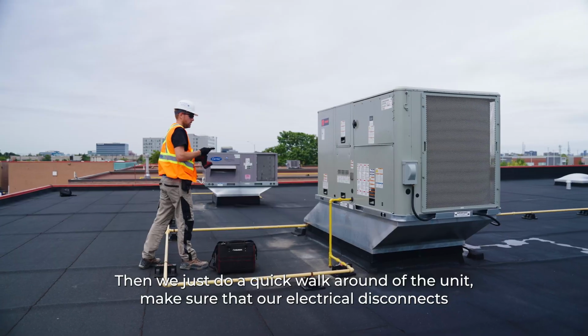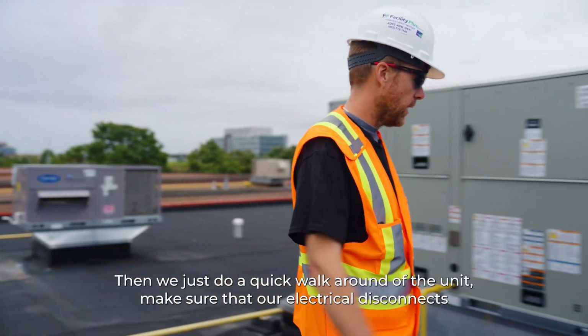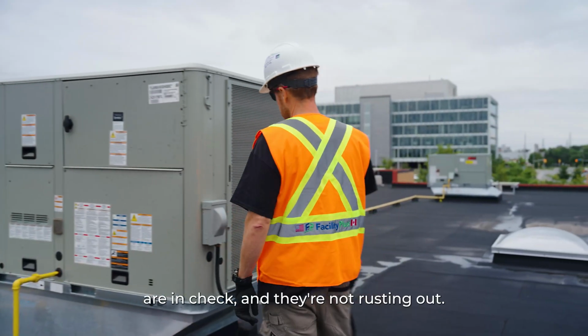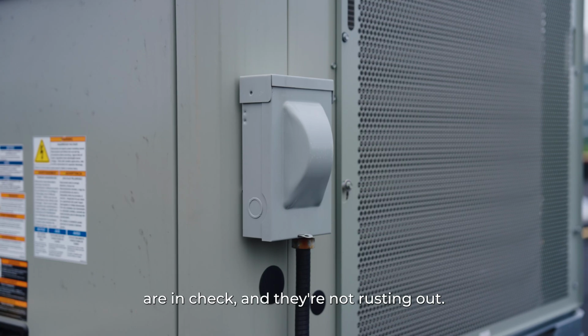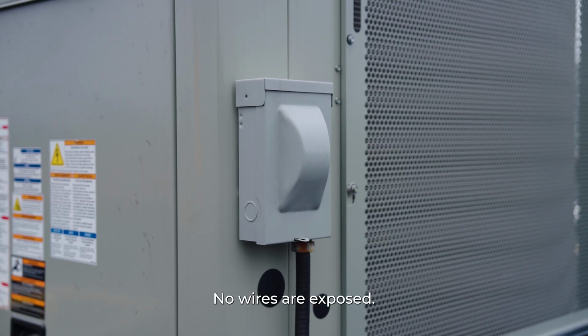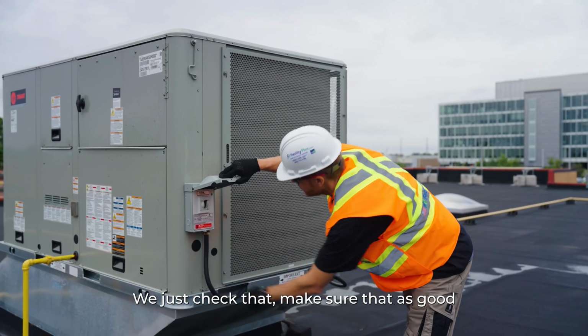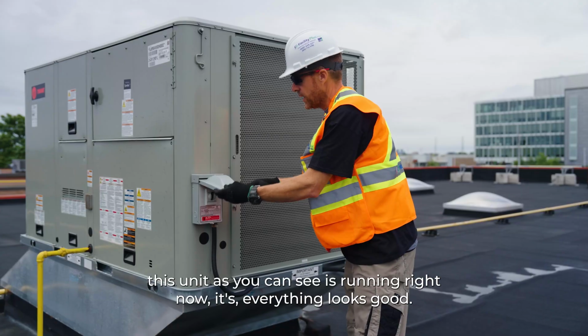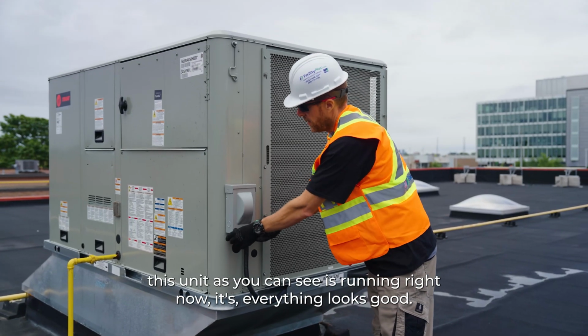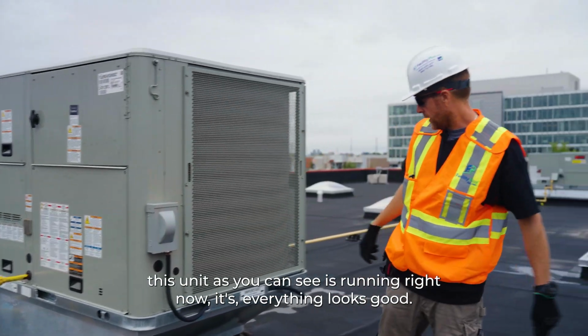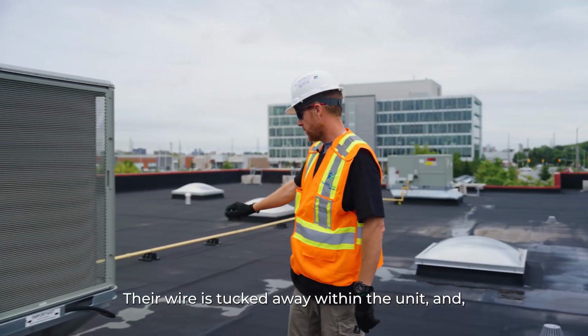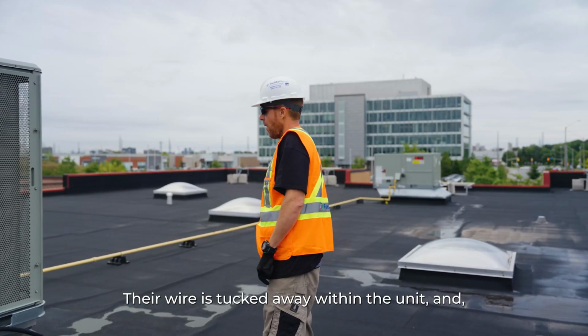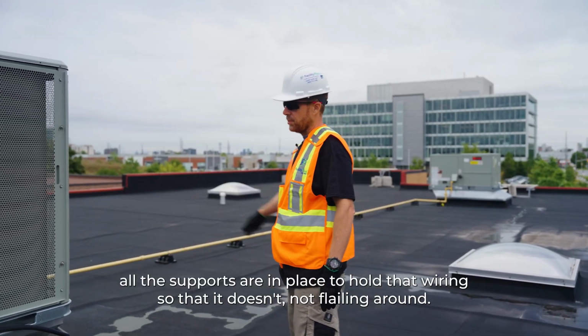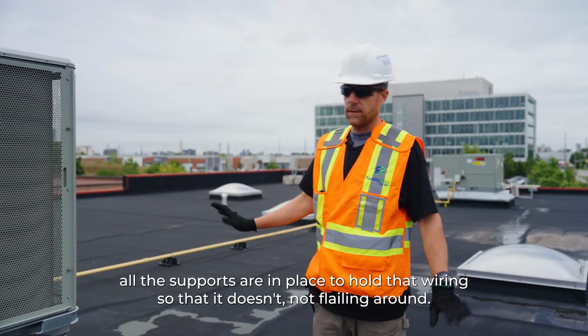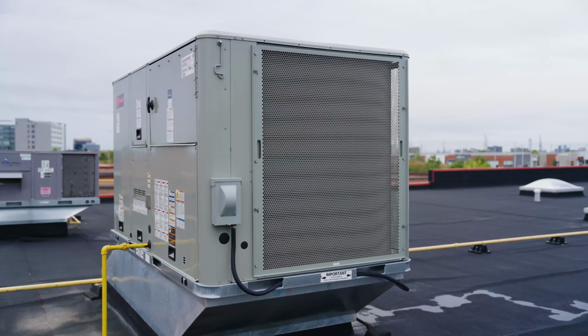Then we just do a quick walk around of the unit, make sure that our electrical disconnects are in check and they're not rusting out. No wires are exposed. We just check that, make sure that is good. This unit, as you can see, is running right now. Everything looks good there. Wire is tucked away within the unit, and all the supports are in place to hold that wiring so that it's not flailing around.